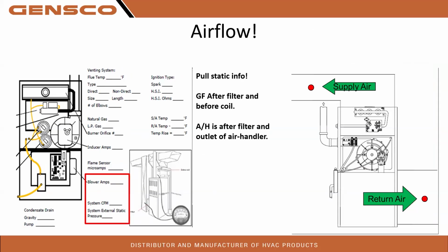So if you know the static number, you can go to the guide and say, okay, at a 0.7 static, this furnace is going to make 650 CFM or whatever that looks like. So pulling static info is going to be advantageous here.